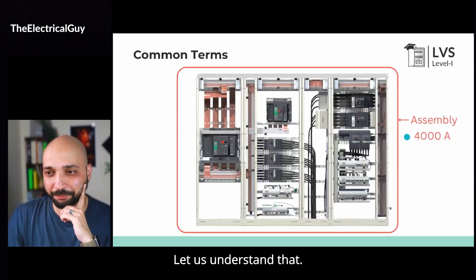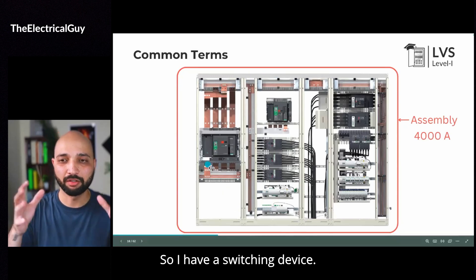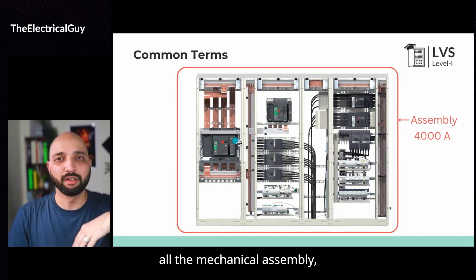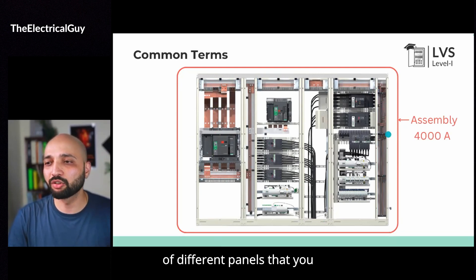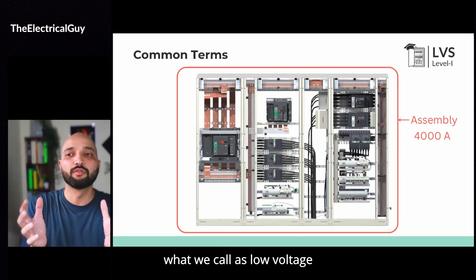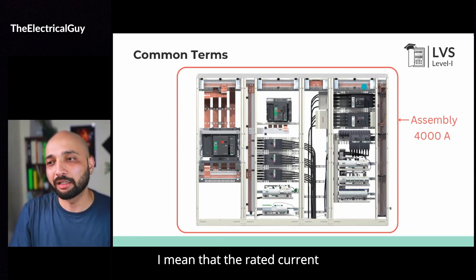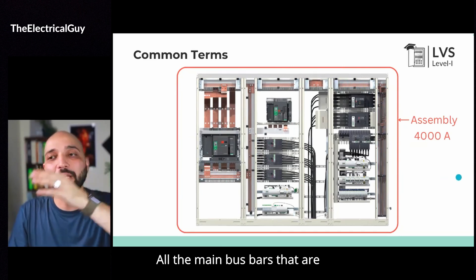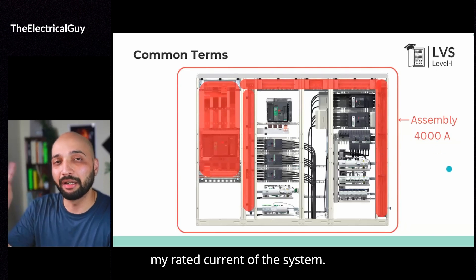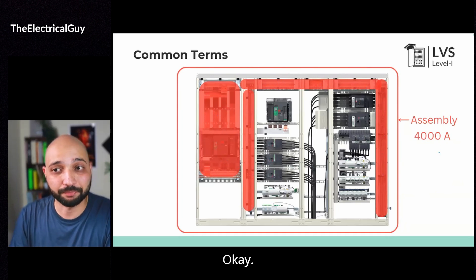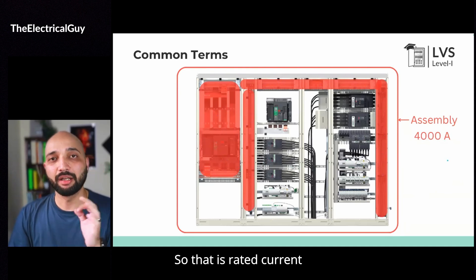Now what is assembly? When I say low voltage switchgear assembly, I mean the complete switchgear combined together. I have a switching device, and to that switching device I have connected everything — all the mechanical assembly. It could be one single panel or it could be the combination of different panels that you can see on your screen. Everything put together is what we call the low voltage switchgear assembly. When I say rated current of my assembly, I mean the rated current of all the main circuits, all the main busbars that are carrying the current. All these busbars should carry the rated current of the system, which is 4000 amperes.